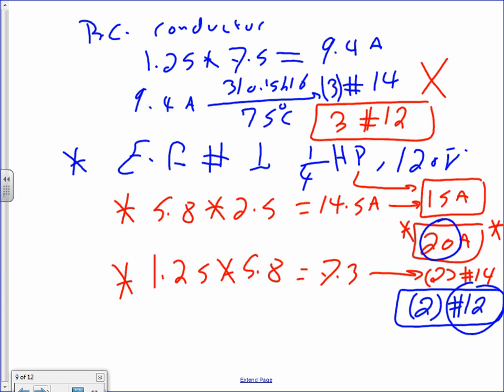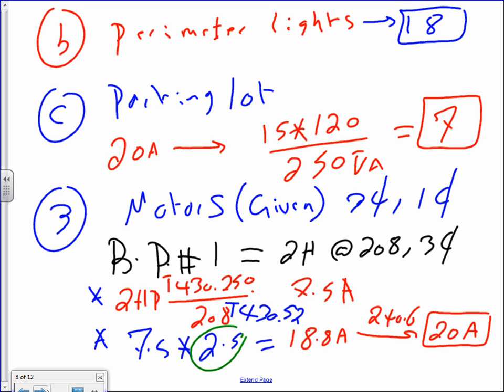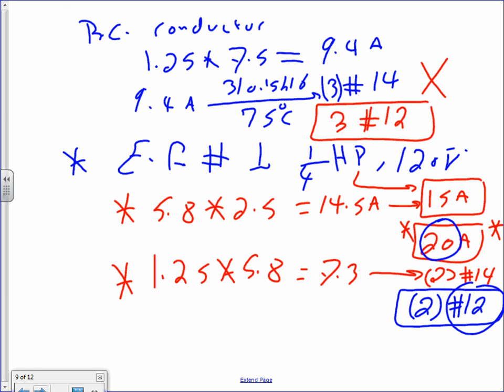Can you guys see how I did an example for you for the pump? That's how you're going to do the branch circuit. I took the boiler pump number 1, took the full load current, found the overcurrent protection device, 20 amps. Then the same thing, find the conductors, multiply by 1.25, get 9.4, number 14, no, 14, we don't use it, we use number 12. Thumbs up, Chad? Typical calculation.